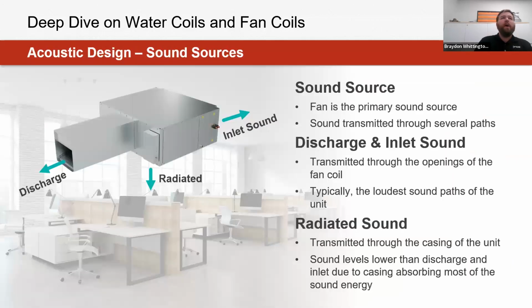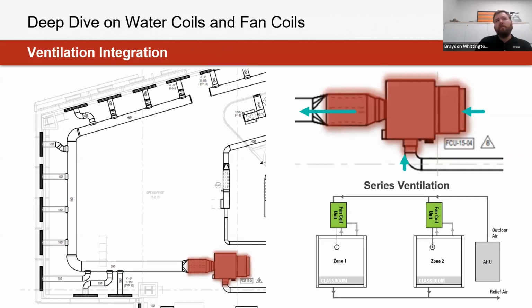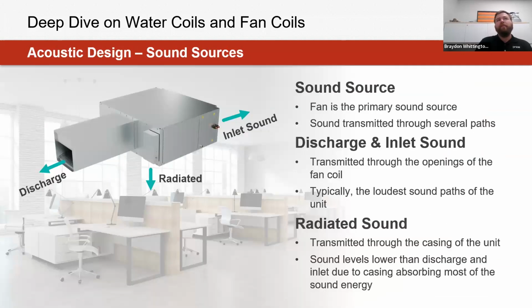And then when looking at even this example being an exposed ceiling application, another consideration that we always have to take into account when talking about fan and blower coils is also the reality of the amount of noise that's going to be emitted from that product. Key driver being just the amount of noise that's being generated from that fan within this equipment, or in the cases of having those fresh air valves from that damper there too. But typically the main driver being that fan.